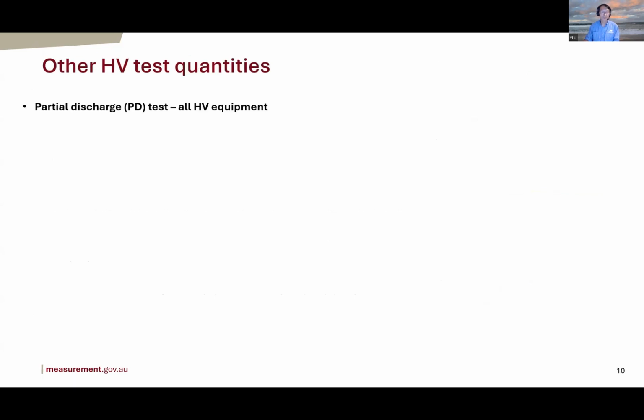Other quantities that you don't see in low voltage measurement include partial discharge. As I mentioned, all HV equipment needs to be tested. You test the so-called apparent charge, the minute charge in the insulation system, and the partial discharge inception voltage, meaning at what voltage level they start to have this partial discharge.